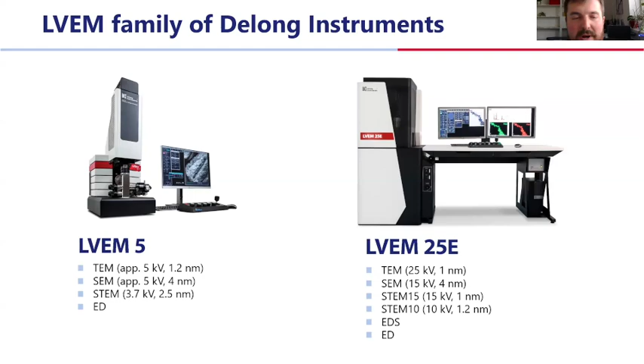Our low voltage transmission electron microscopes operate at accelerating energies between 5 and 25 kiloelectron volts. And because of this low energy approach, they offer several unique features and innovative technical solutions that conventional high voltage TEMs simply don't provide. On this slide, you can already see a brief summary of these unique aspects of our technology. But before we jump into the details, there's one important question which should be answered first. Why should you prefer low voltage TEM instead of a conventional TEM operating at 80, 100, or even 200 kiloelectron volts? The answer is very simple.